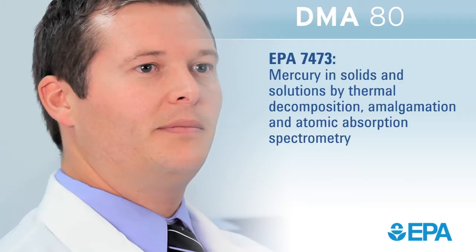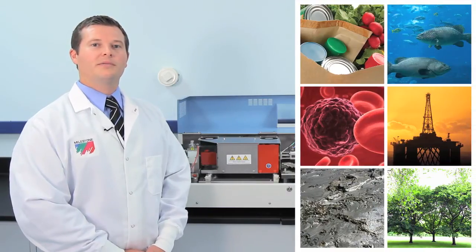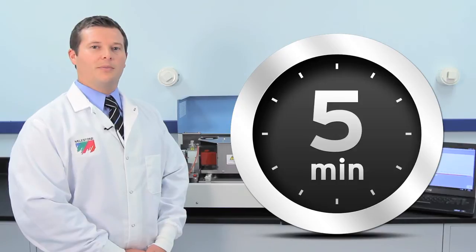U.S. EPA Method 7473 was developed using the DMA80. The method is widely used in food, environmental, and other industries. Detection limits are in the PPT ranges, even on solid samples, and total analysis time is six minutes per sample, and of course requires no sample prep.